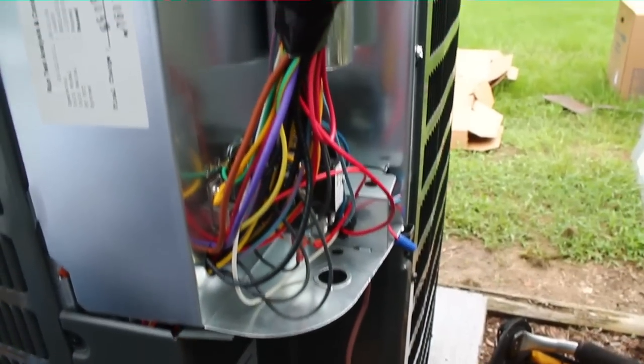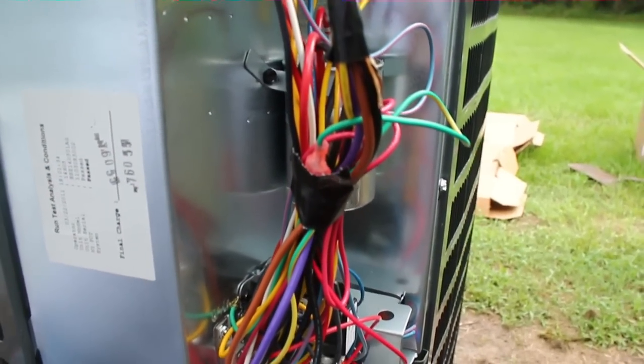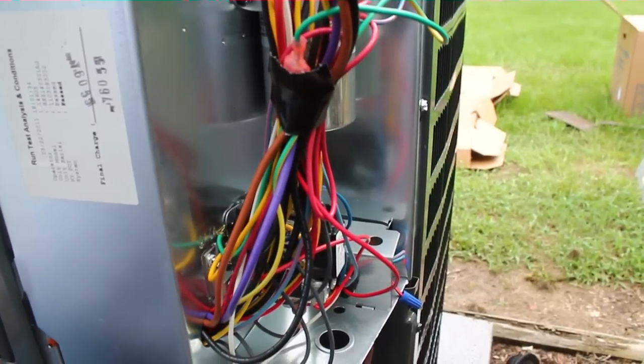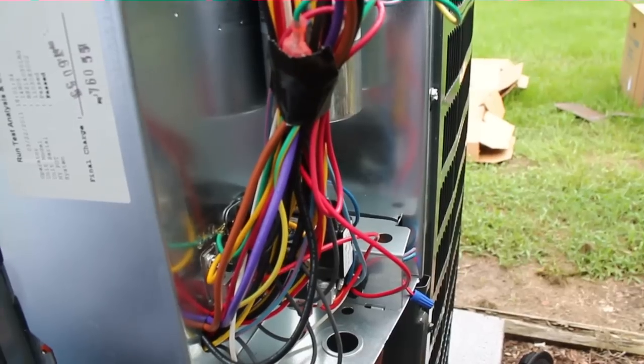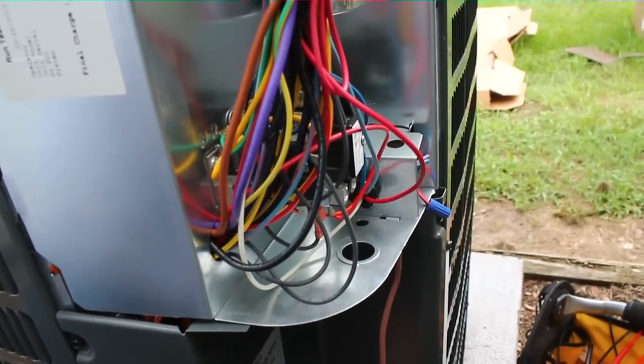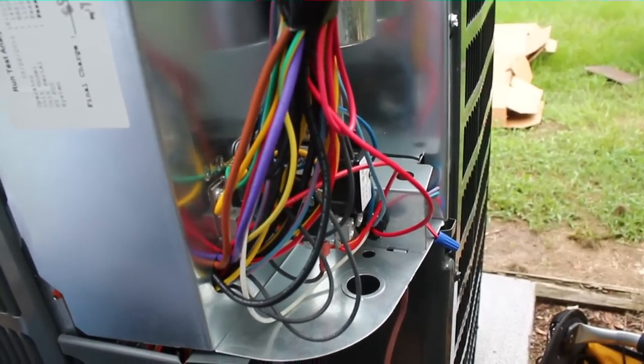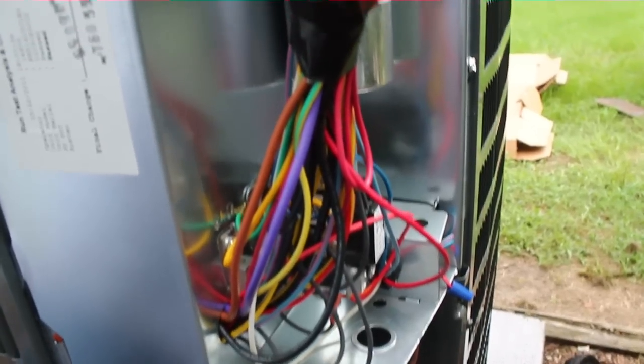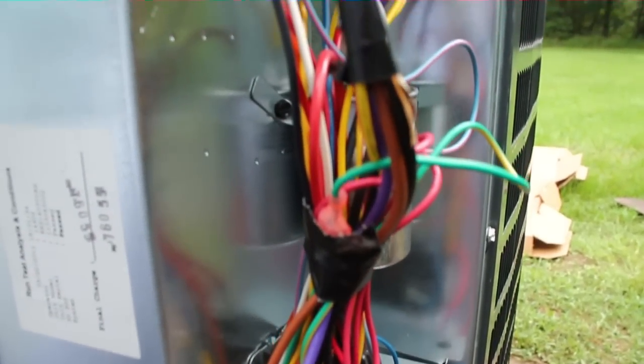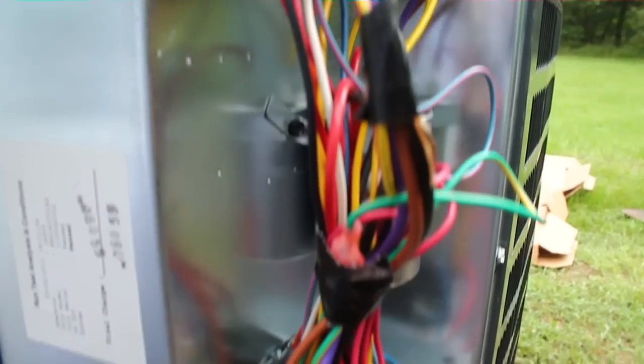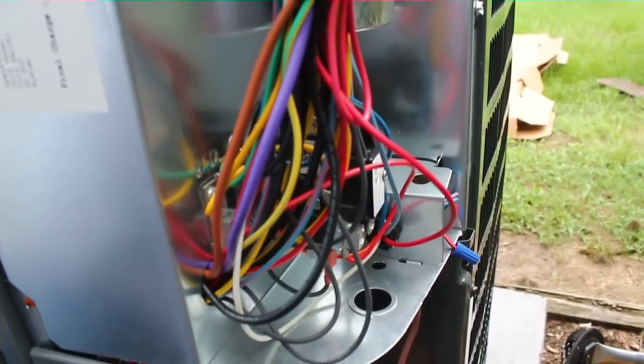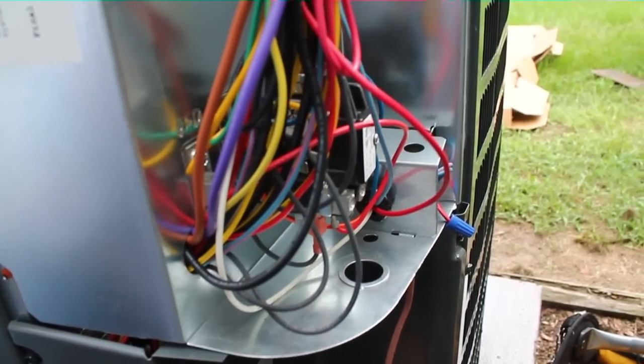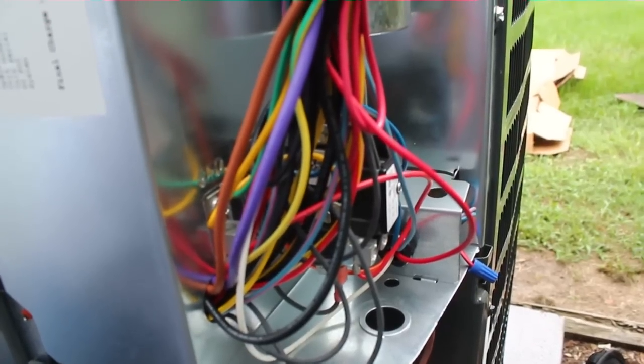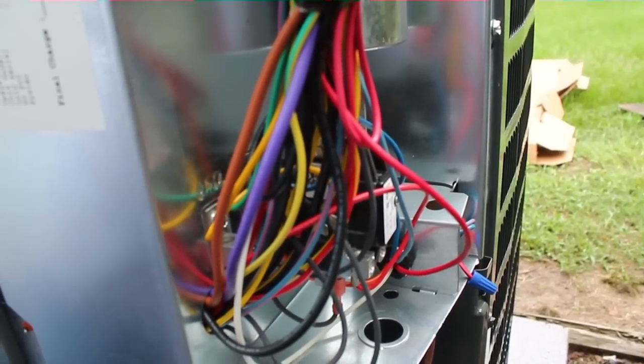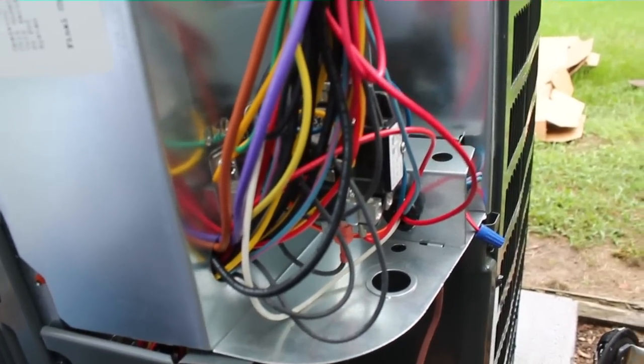I've wired up the low voltage, 5 wires coming in. You have a white W2, you have a red for 24 volt hot, you have a blue 24 volt common, an orange reversing valve, and a yellow typically, but on the Goodman condenser it's like a bluish wire with a red stripe. It's for the contactor.